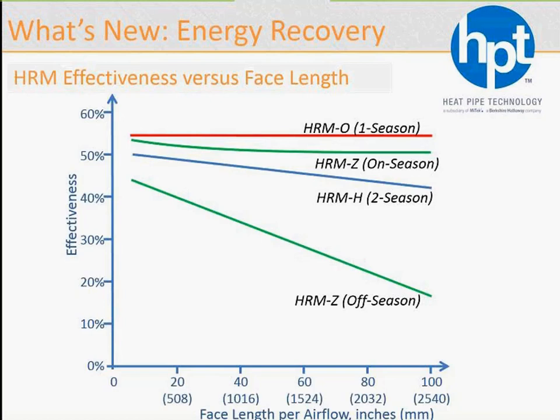For shorter heat pipes, it actually starts a little higher than 40%, but as the heat pipes get longer, almost to the max, it drops to about 20%. So since you're shooting for a particular season, the other season may not have too many BTUs, but even then, you're doing fairly good recovery in the off season.